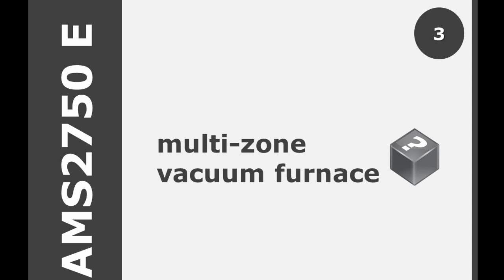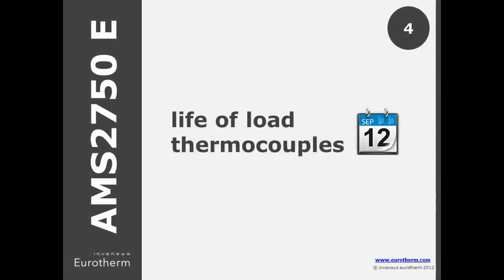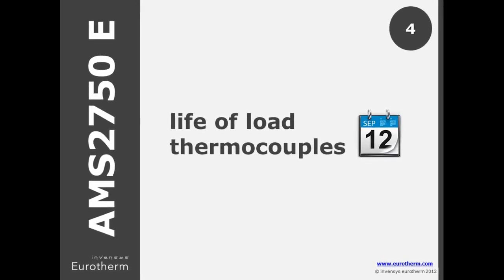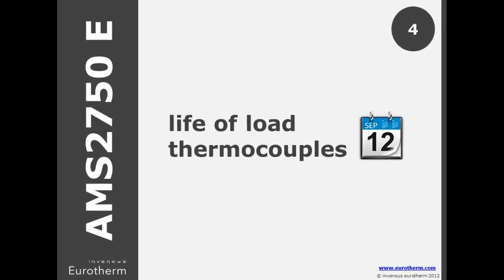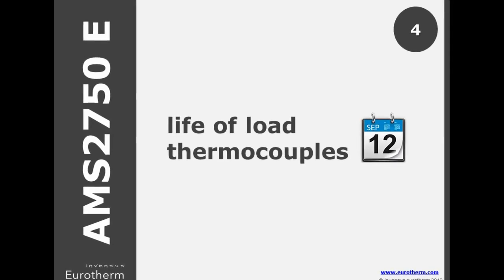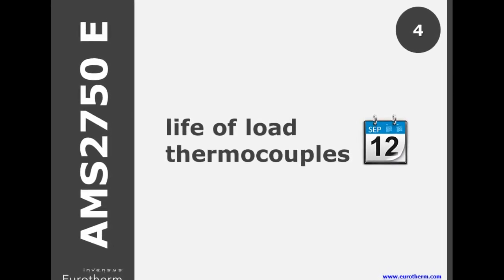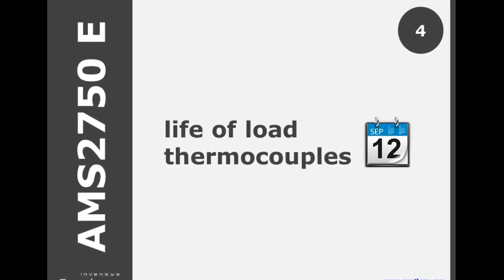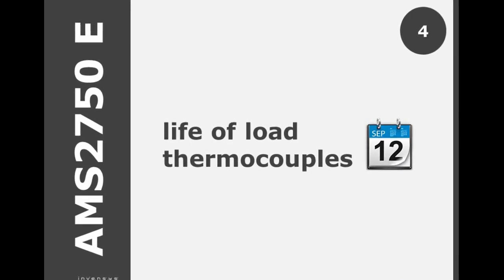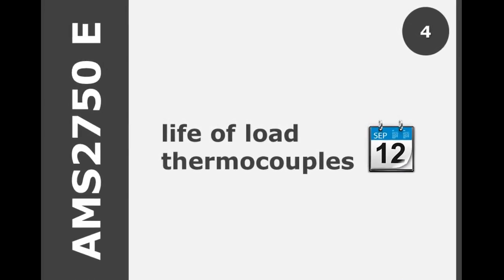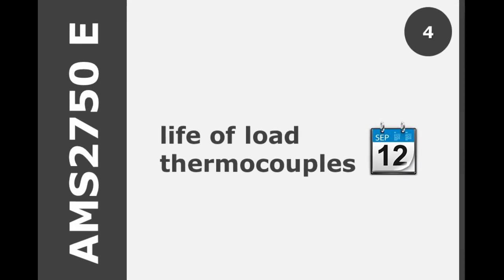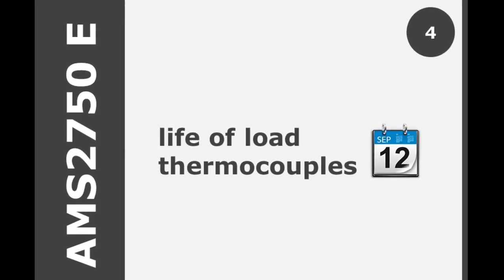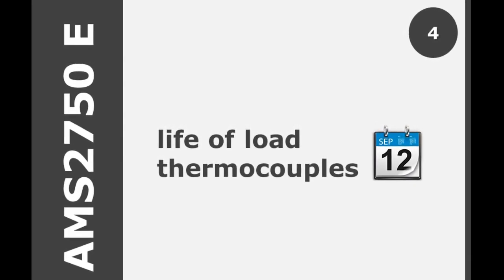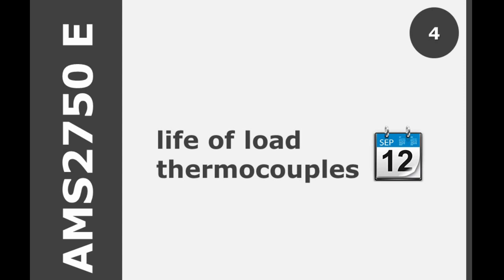For non-expendable load thermocouples, it is prescribed how many days to use or maximum uses at temperature. In E, at 2200 to 2299 degrees Fahrenheit, there now is a time period added of 3 months, or the 10 uses as specified in D. For 1801 to 2199 degrees Fahrenheit, this has now been lengthened from 30 days to 3 months, and keeps the 90 uses specified in D.